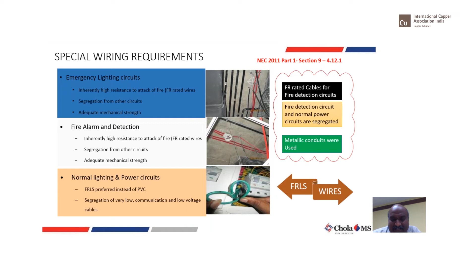Okay, the sizing part, of course, depends upon the type of load connected to the last circuit. If it is going to be an air conditioner, a system, a phone or a light, the load determines the size of the cable. Here, what we're trying to say is what type of cable to be used, whether it is FRLS or PVC. As far as possible, knowledge levels have improved in the market. People have stopped using PVC or have upgraded to FRLS. There are old buildings which are still running on PVC, which has certain danger when there is a fire.